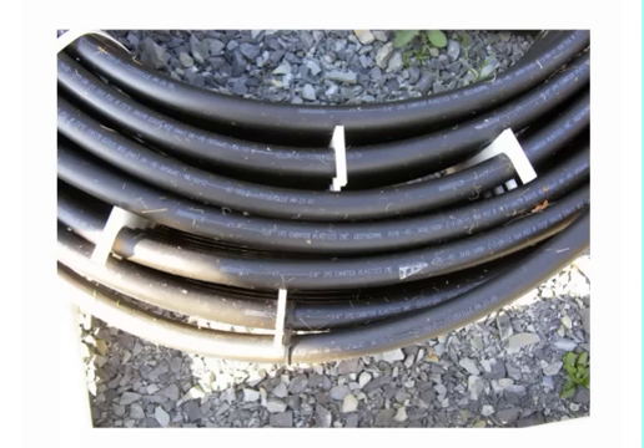It's important to make sure you have proper spacing and you're using all the surface area of the tubes. We don't put in a lot of spare capacity here, folks. Just taking a 300-foot coil of pipe from your vendor, banded together, welding it up with headers and kicking it into the pond, you're going to have problems, I promise you. So make sure you're doing it properly.